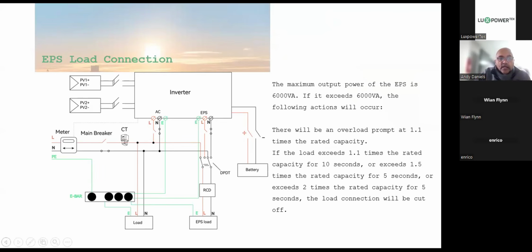So here you've got your meter coming in, mains breaker, there's the CT. It goes into the AC in, and then it goes to the changeover. And then from the output, we have our residual current breaker here, or the ELCB, earth leakage circuit breaker. Remember that the only thing that we have in common is the earth bar. This neutral and this neutral will never see each other. These neutrals are always separated. So here we have a typical layout.